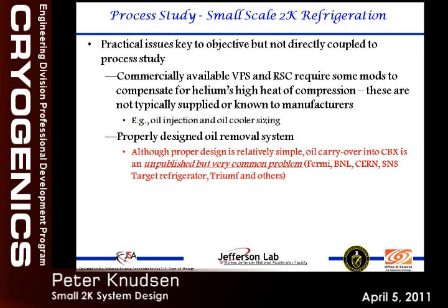And it's worth mentioning here, which is why it's in red, that this is actually very important because that is a very common problem in many systems, and especially for subatmospheric systems, you don't need any more things that will limit the amount of uptime that you have on a 2K machine, because that oil carryover will degrade your oil removal system, and therefore you can have contamination problems.